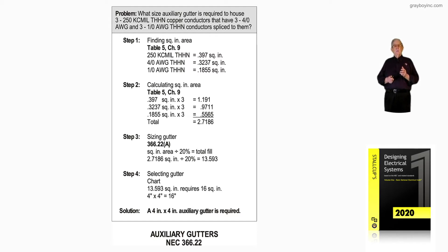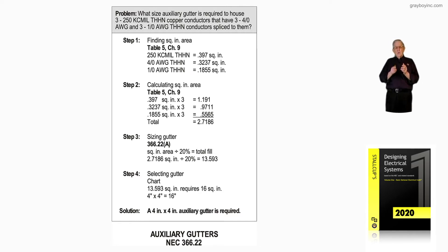Step one is going to Table 5 and based upon THHN and the size conductors that you see in the illustration, we come up with a cross-sectional area of each conductor based upon the size of the conductor, the insulation of the conductor, and the material of the conductor, which is copper in this case.